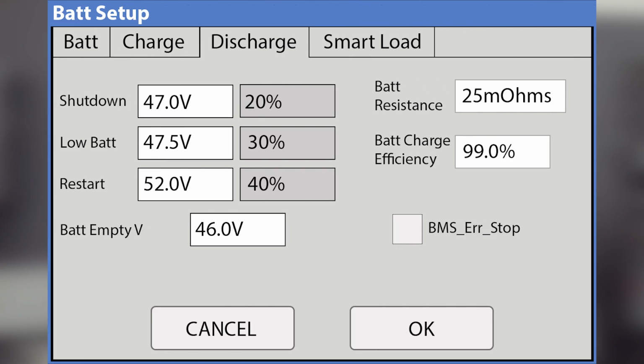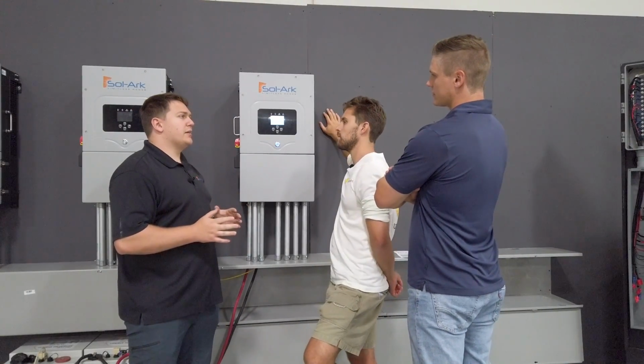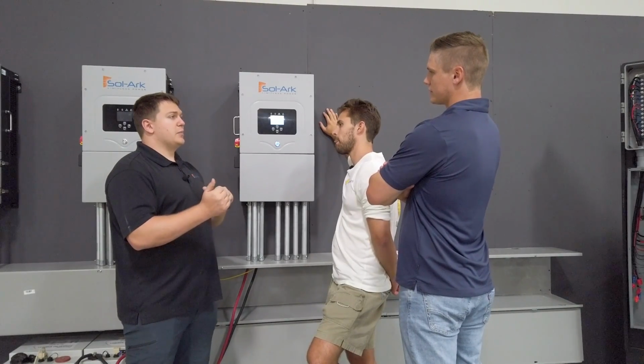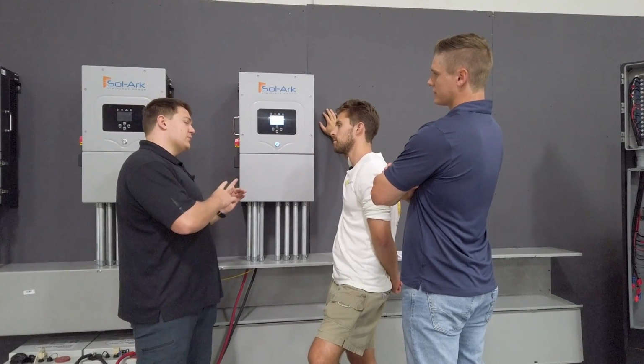Moving right along to the discharge tab. So here we have that setting that I alluded to earlier, which is the battery resistance. That's going to be in milliohms, and we use that value to, in real time, do Ohm's law adjustments for all your set points if you're in voltage mode. So if you're pulling a whole bunch of amps out, we're going to allow that voltage to drop accordingly based off how much resistance you've programmed into the unit. So if you ever think that your generator should be kicking on right now because the voltage is where you set it to, but you're actually pulling a bunch of power out of the battery, this is why it hasn't triggered yet.